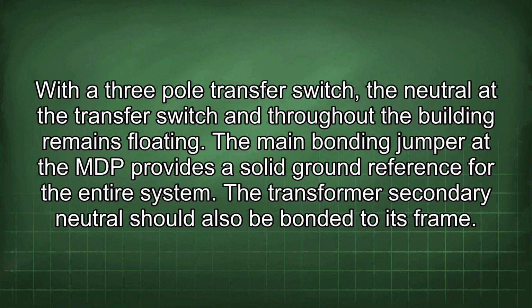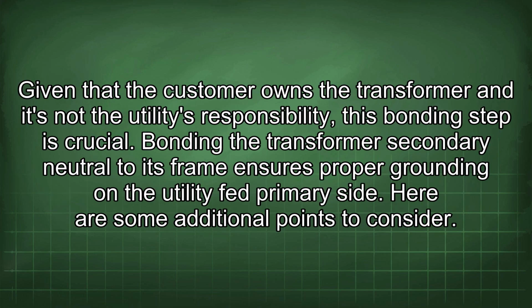The transformer secondary neutral should also be bonded to its frame. Given that the customer owns the transformer and it's not the utility's responsibility, this bonding step is crucial. Bonding the transformer secondary neutral to its frame ensures proper grounding on the utility-fed primary side.